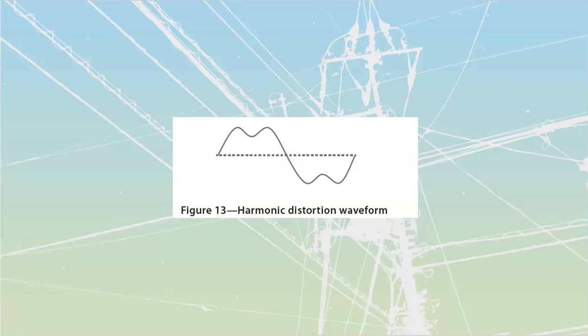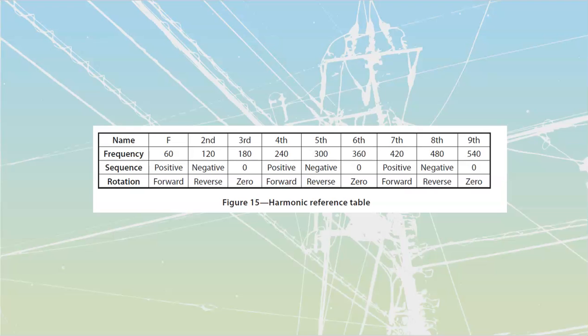This is what a good AC waveform is supposed to look like. Now I'm able to get harmonics. We call this first one our fundamental frequency, or our 1st harmonic, the best one, at 60 hertz. Harmonics are just multiples of that: my second harmonic is 120, my third is 3 times 60, or 180, and my fourth is 4 times 60, or 240.